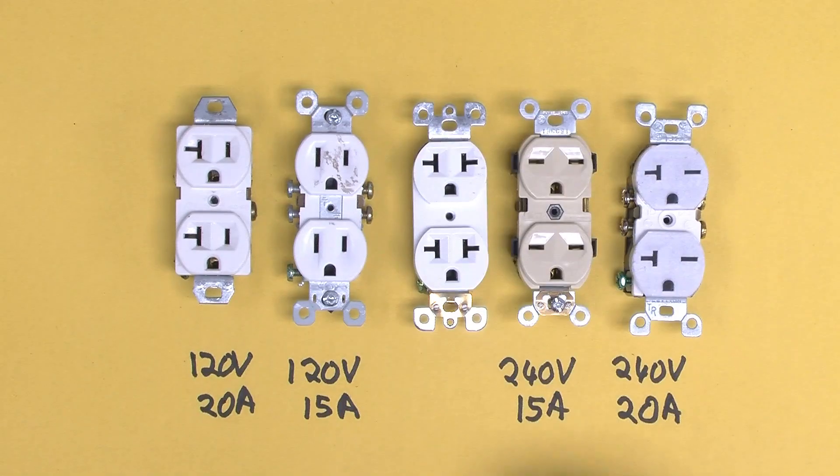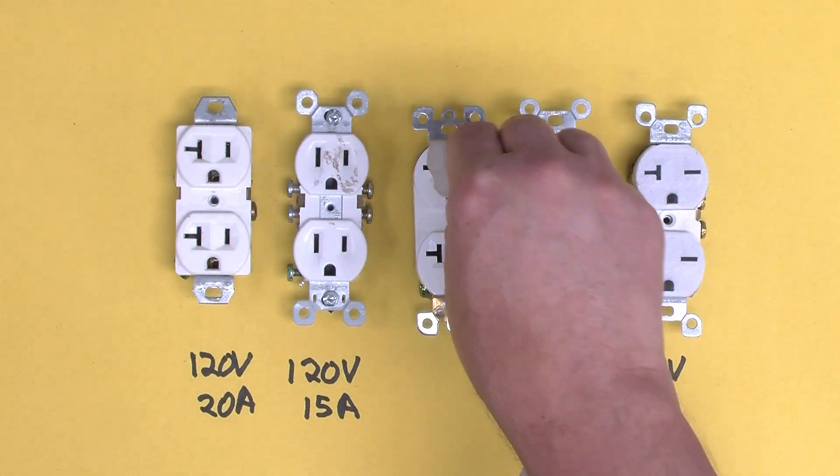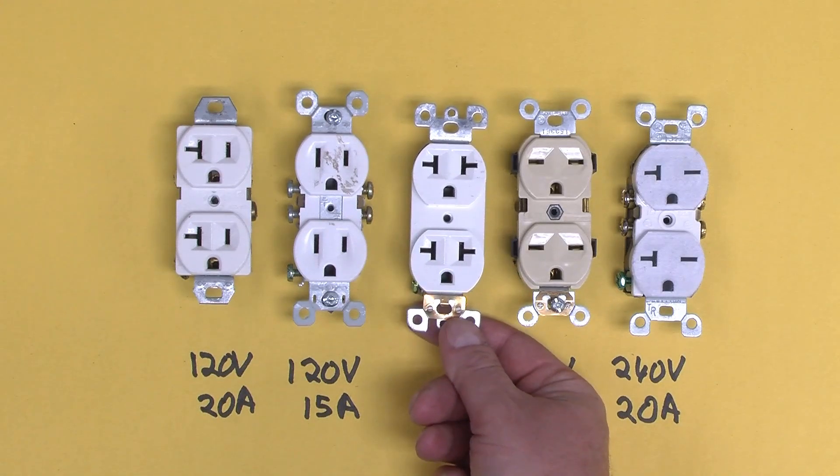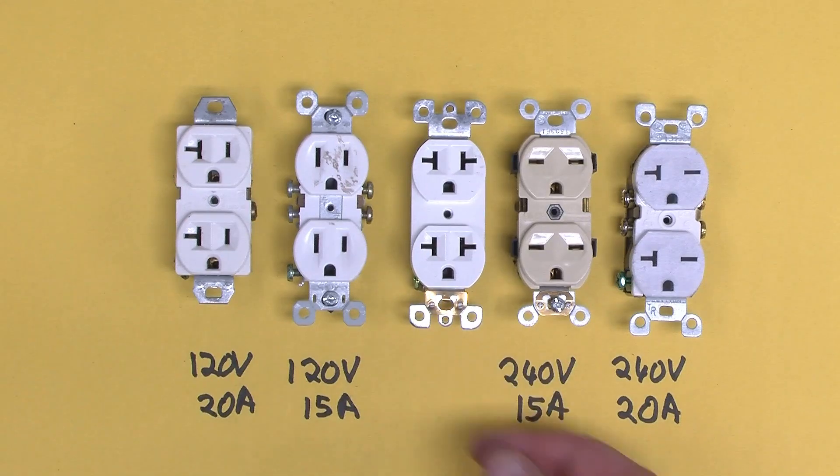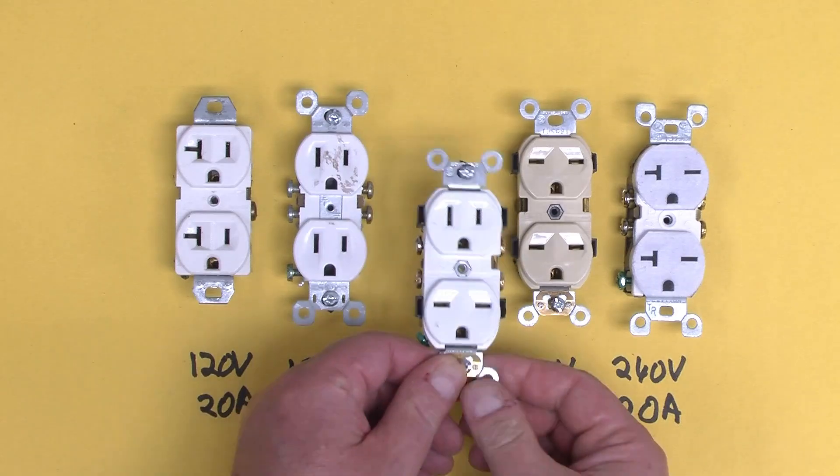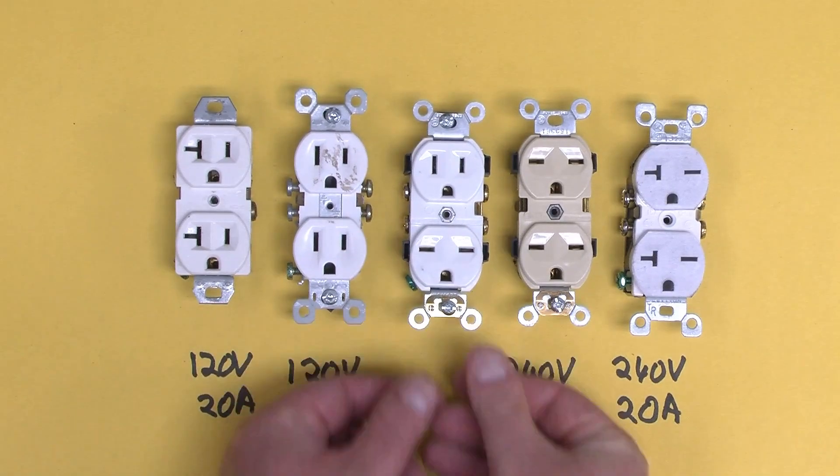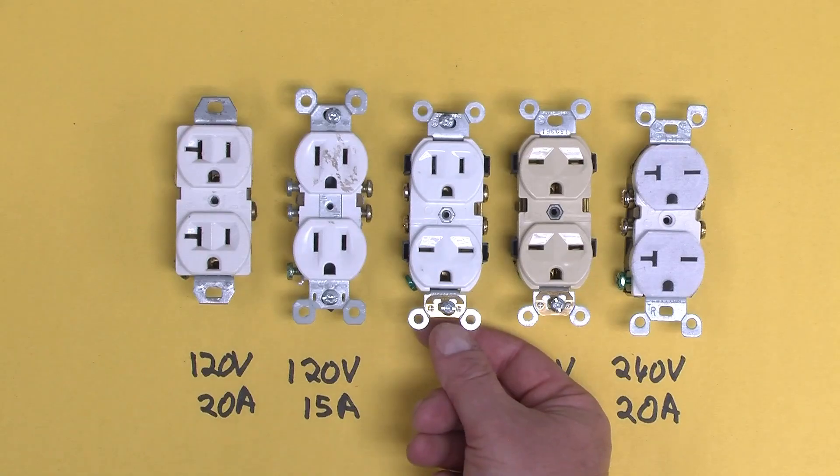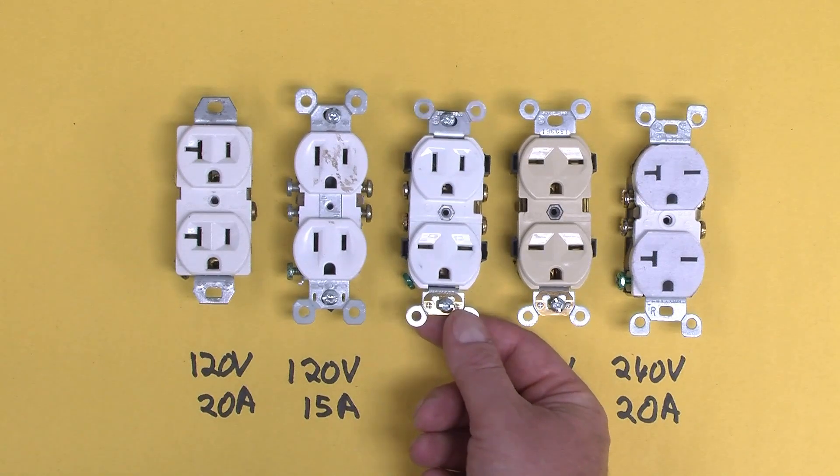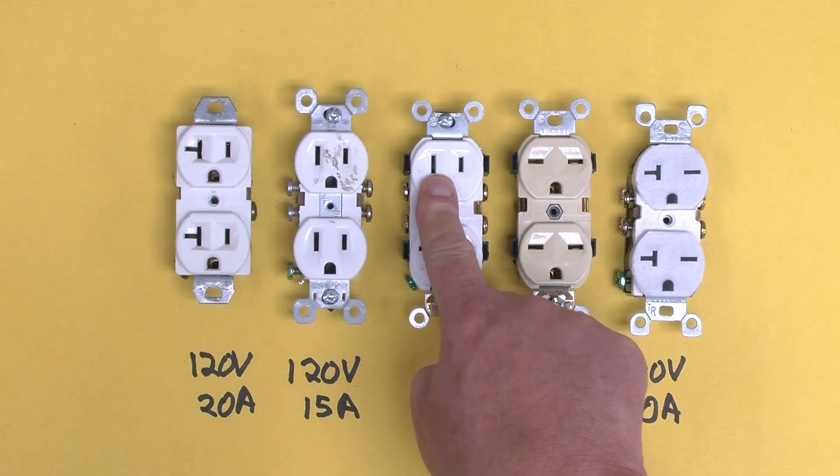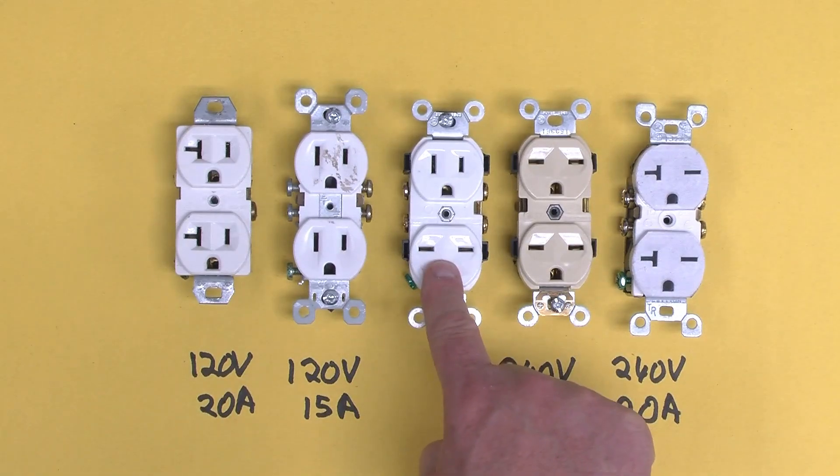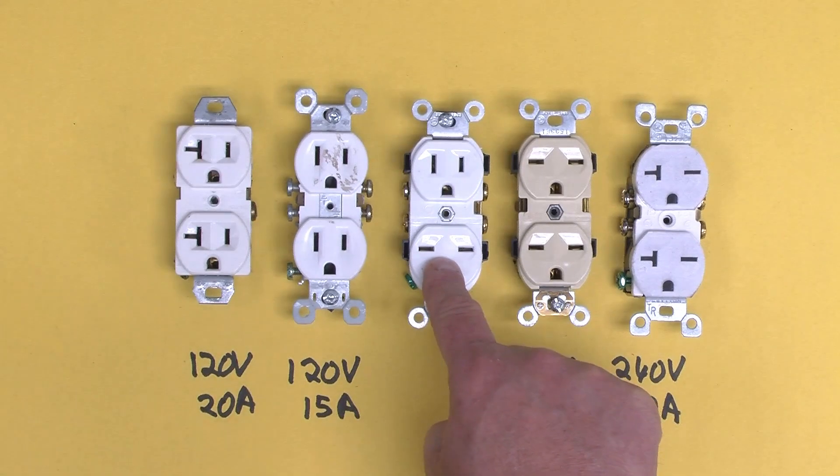If you do happen to need a receptacle that you could plug either in and get the right voltage, luckily there is one that does it, and that is this one, which is an official receptacle. It's made by Leviton, part number 5031, in this case W because it's white. It has a proper 120 volt receptacle up here and a proper 240 volt one down here.